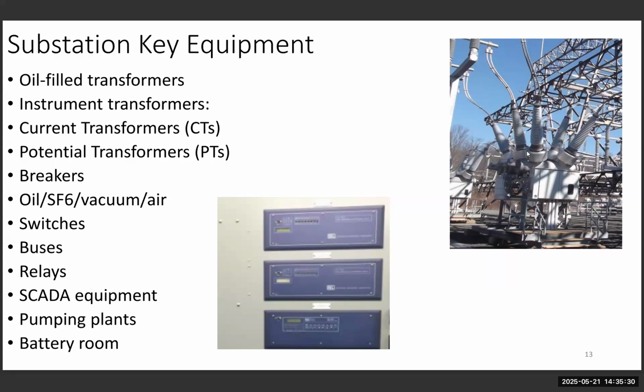So again, the breakers are great candidates for substation intelligence because the breaker provides a very important function. If there's a failure and the breaker doesn't operate, we're going to have a major issue. You could have a fire, you could lose the whole substation. So that's very, very important. We use a lot of switches. Pretty much every important device you could think about, like a breaker or transformer, is going to have one switch on either side to be able to take that component out of service. So we need to always have the means to operate in normal and emergency conditions.